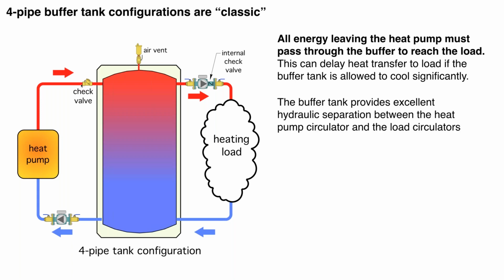Now, one of the nice things that a 4-pipe configuration does, it provides what's called hydraulic separation. And if you're new to hydronics, this is a really important concept. Anytime we have 2 or more simultaneously operating circulators in a system, the ideal scenario is we don't want those circulators interfering with each other. And imagine one is a larger circulator and one is a smaller circulator. If you run them both at the same time and you let them interfere with each other, basically think of circulators as bullies on a playground. The big circulator is the big bully, and the big circulator is going to dominate the pressure dynamics in the system, and that can cause flow problems for the small circulator.